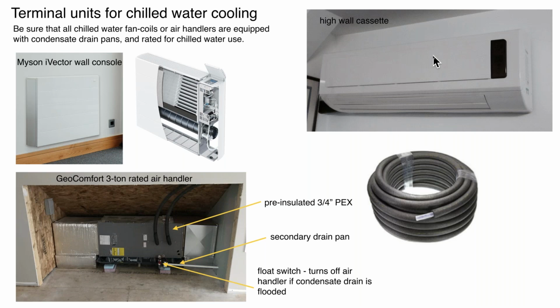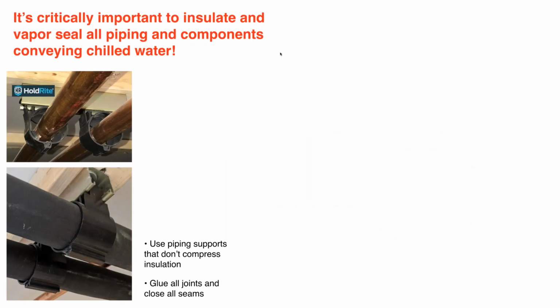Again, I'm sure most of you recognize this is a high wall cassette. This is very common when you have a ductless mini split system. Basically, it's the same unit with a water coil in it instead of a refrigerant coil, and that can be used for heating or for cooling. So again, you have options. You can do single zone whole house air distribution, or you could do room by room or area by area distribution with either wall mounted or low wall mounted or high wall mounted fan coils. Now, I mentioned earlier, be very careful with chill water.